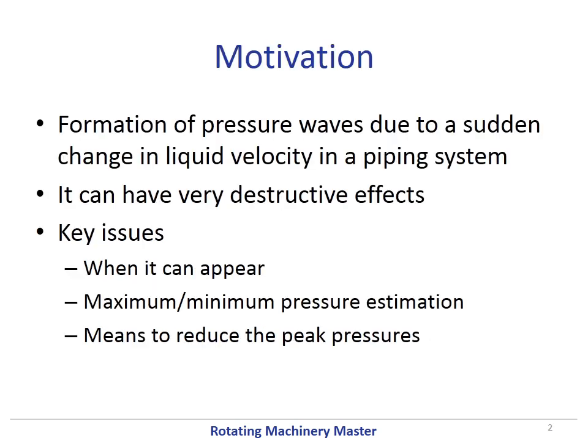Water hammer is the formation of pressure waves due to a sudden change in liquid velocity inside a piping system. It can have very destructive effects. The key issues for the practitioner and the designer are when it can appear, what is the maximum or minimum pressure estimation, and what means do we have to reduce the peak pressures.